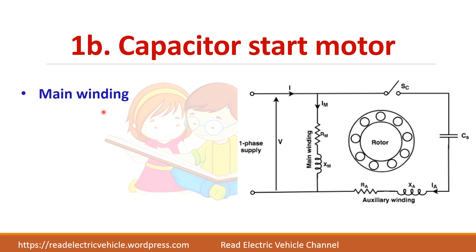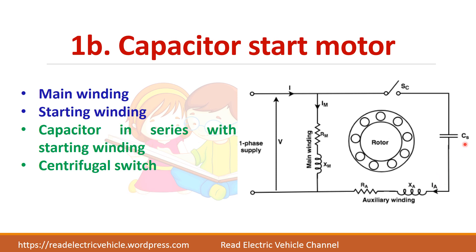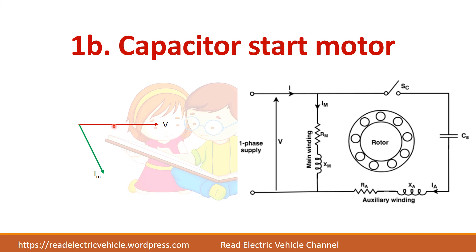First we will see the capacitor start motor. The capacitor is used only for starting purpose. In the auxiliary winding, the capacitor is connected in series through a centrifugal switch. After starting, this switch will be opened so that the capacitor and auxiliary winding will be removed. In the phasor diagram, the main winding current IM lags the voltage V, while the auxiliary current IA leads the voltage by some angle because a capacitor is connected.